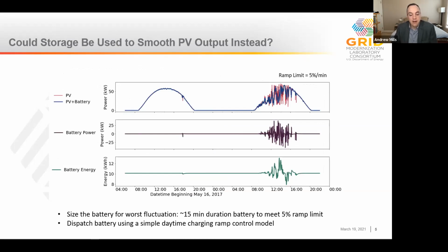Alternatively, we recently evaluated an often discussed strategy of trying to smooth PV ramps at an individual plant using storage. Here you can see how we simulated the operation of that battery, using it to limit the ramps from that individual PV plant. On a partly cloudy day, the battery is rapidly charged and discharged to limit the aggregate ramp of the PV and battery system to about 5% of the PV capacity per minute. We sized the battery power rating similar to the PV plant, but the amount of energy the battery needed to store was relatively small, so at full power this battery could be fully discharged in just 15 minutes.